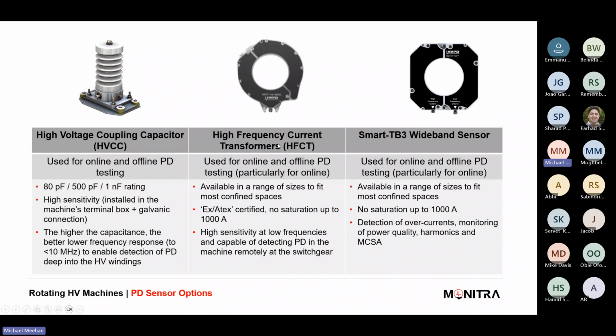A high voltage coupling capacitor is exactly what it says. This will be fitted inside the motor terminal box. You've got the HT connection at the top here, which will be connected directly to U, V and W. There'll be one per phase. That's how we get the phase resolved pattern. We're looking at PD from each phase, and that's how we get the ability to look at which phase potentially has issues, based on time of flight measurements and correlation between PD patterns.